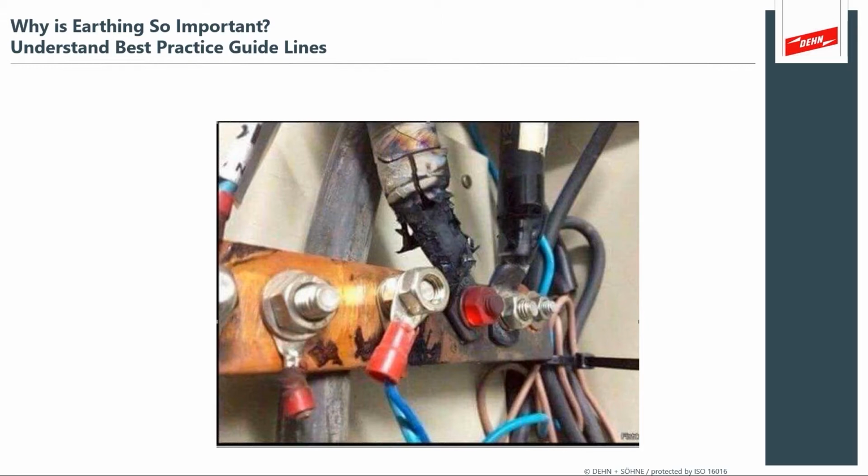Well, a photograph like this tells you a lot about what's going on in this particular plant. And here you can see something that looks like a quarter 20 nut that's just glowing red cherry hot. So you know that there's a lot of things going wrong here.